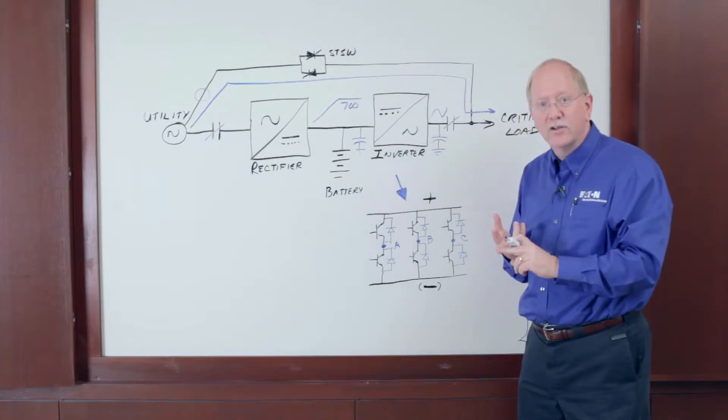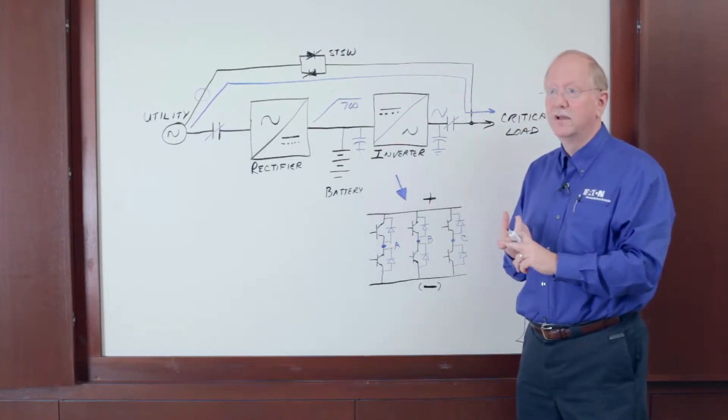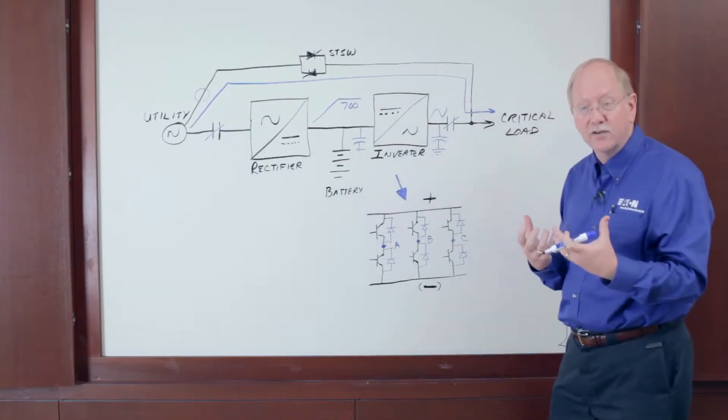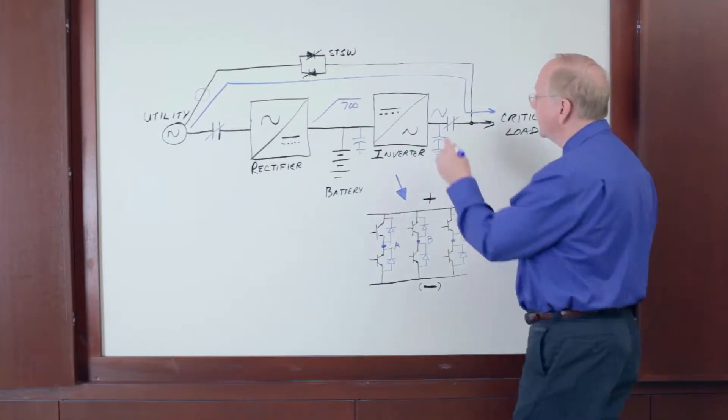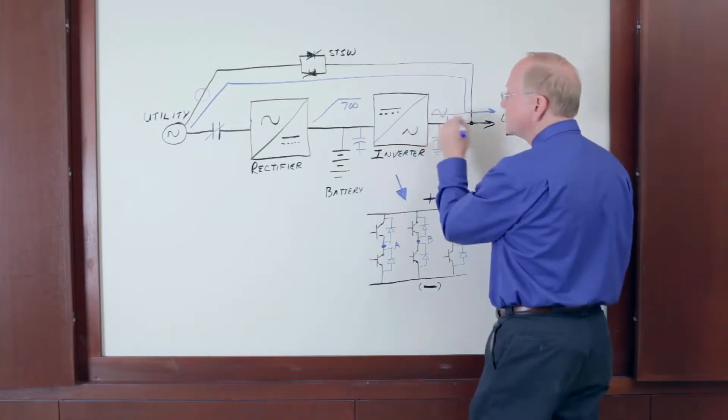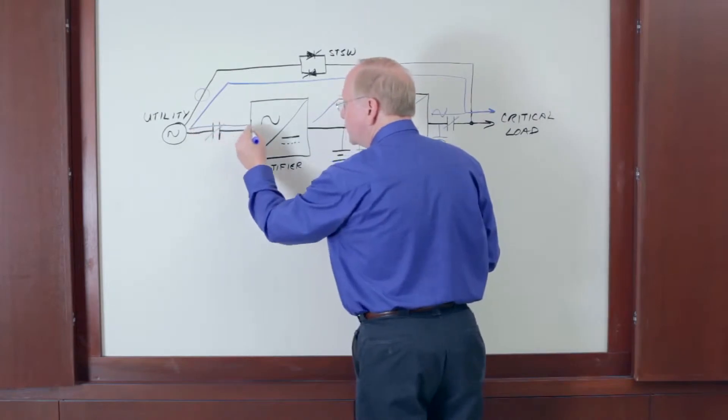That gives us two benefits. I don't have to wait for the contactor to close and I don't have to hope it'll close. A contactor that is closed can't fail to close. It eliminates the mechanical component here. So with closed contactors, I have voltage here and I have voltage here.